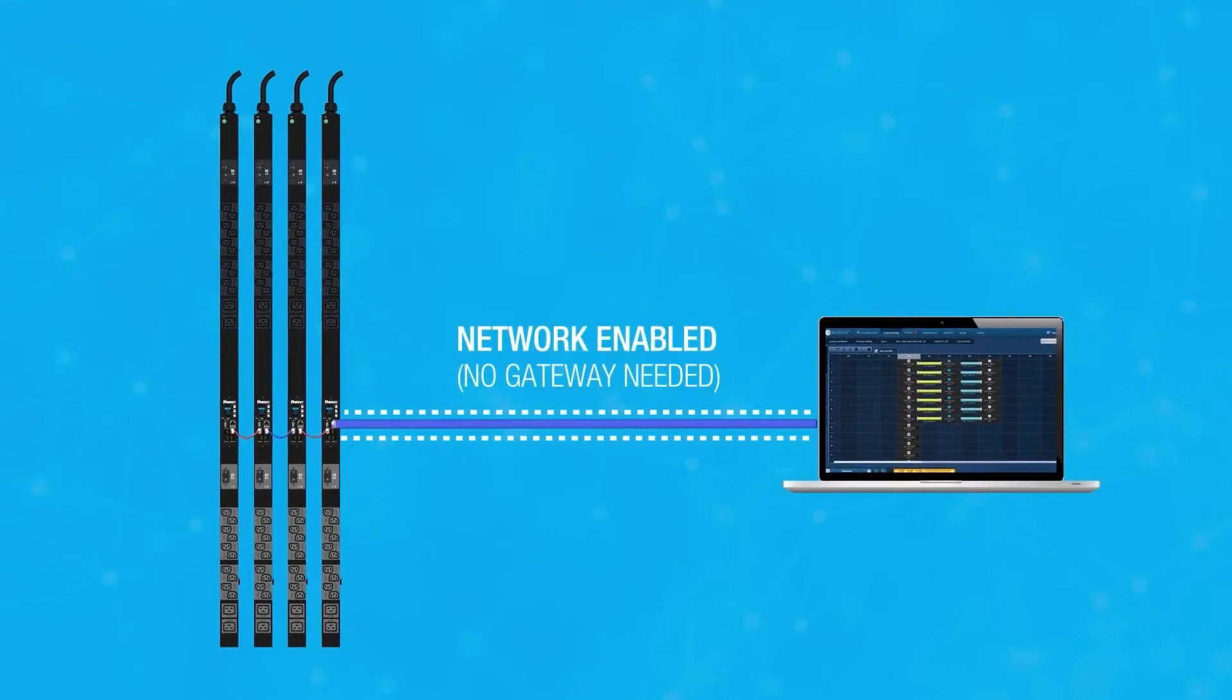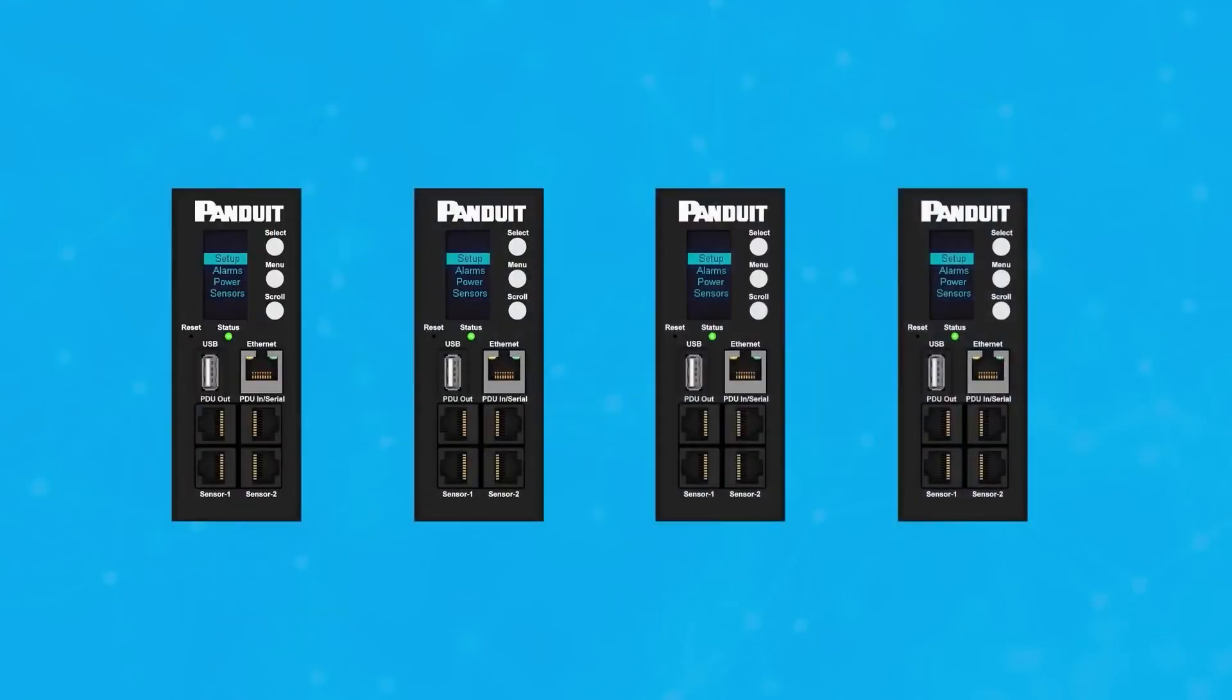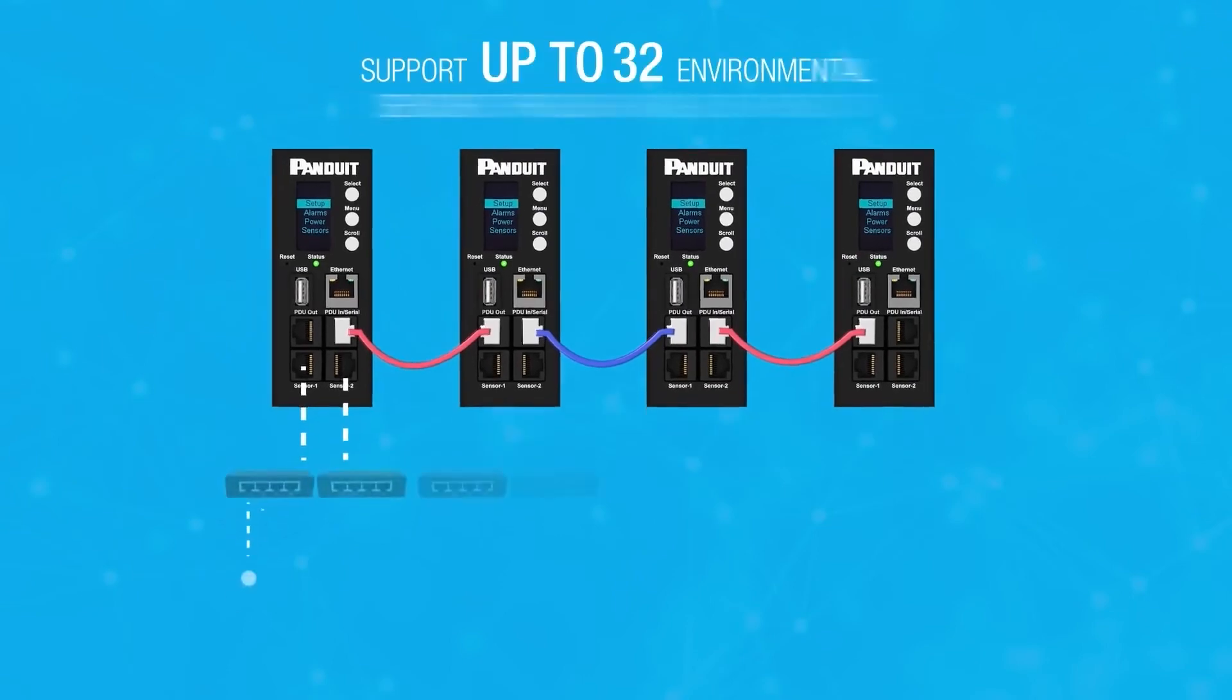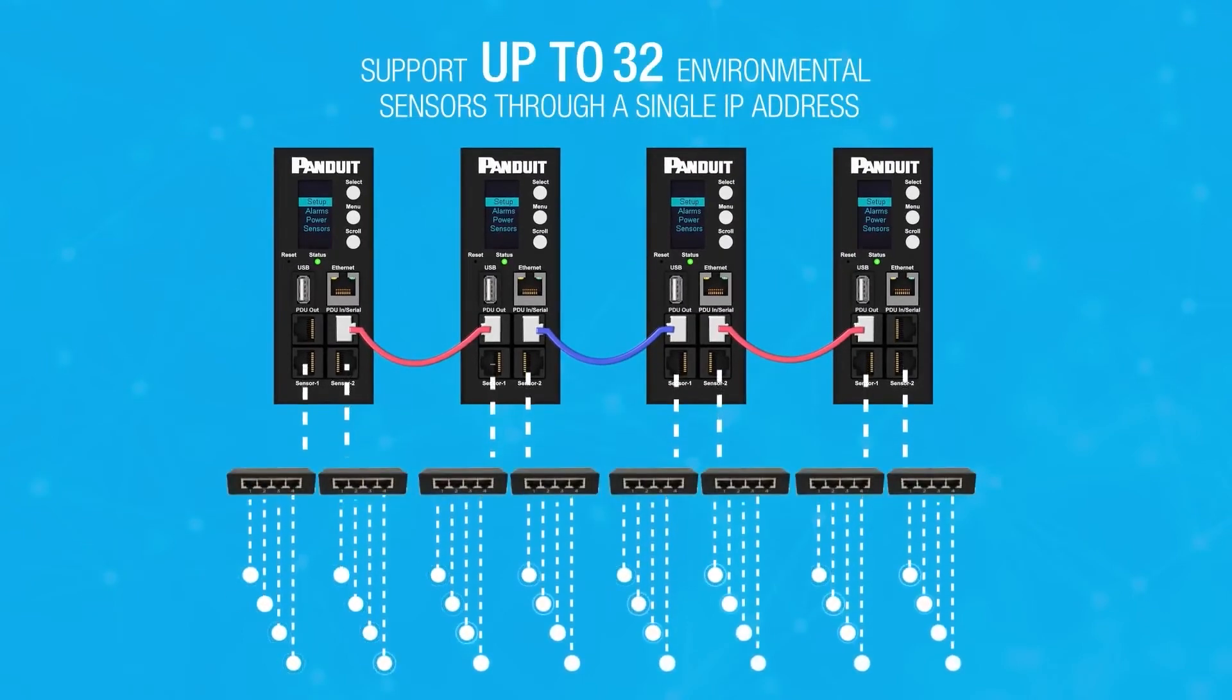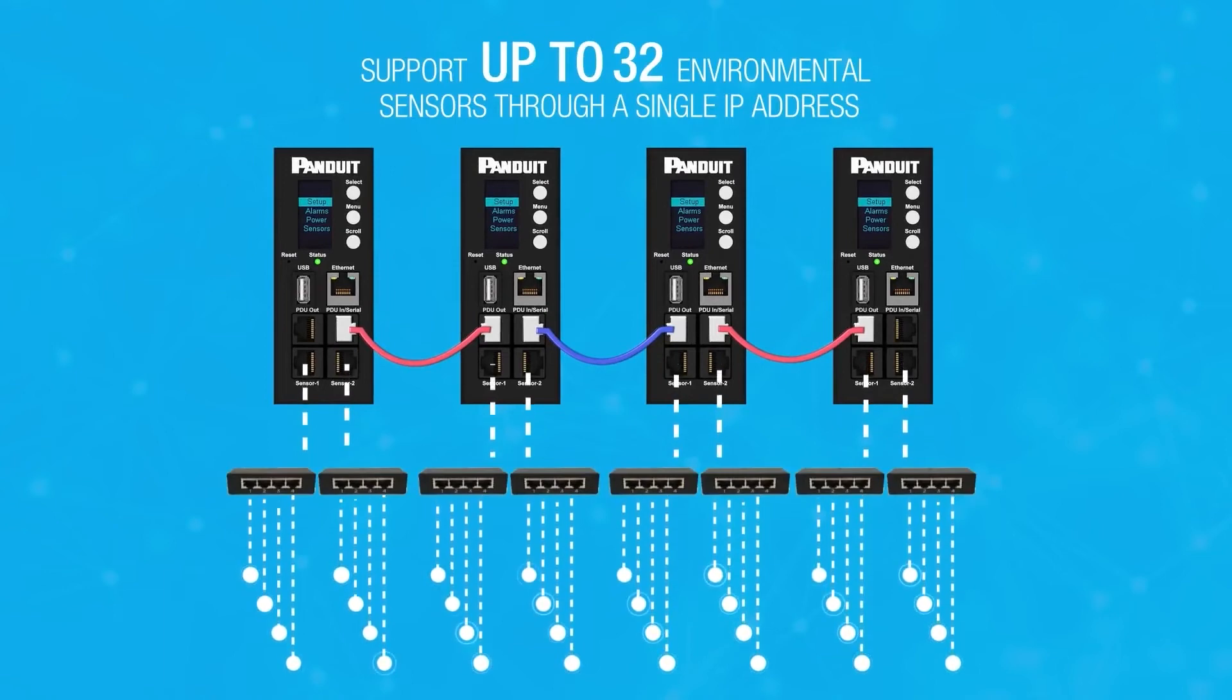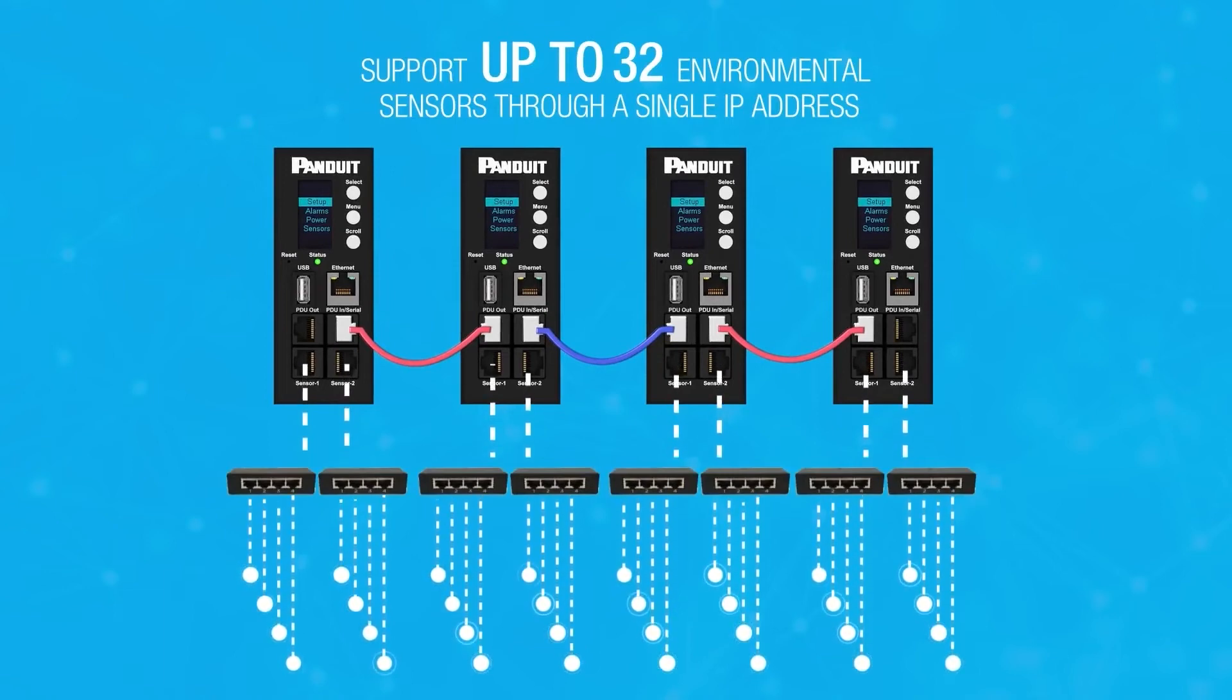Now the intelligence doesn't stop there at the power level. There are a series of serial ports that allow you to daisy chain four PDUs together, which opens up 32 additional environmental sensor ports. That's all done under one IP address, which helps simplify installation and day-two and beyond operational scenarios.